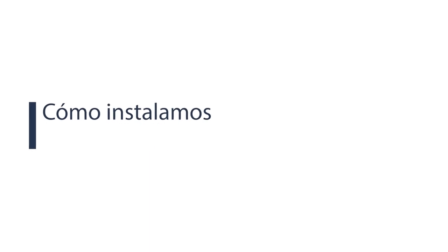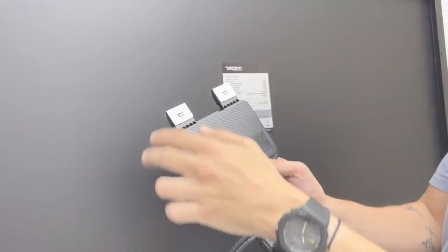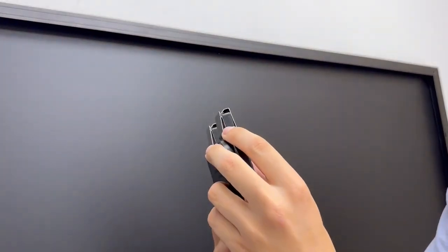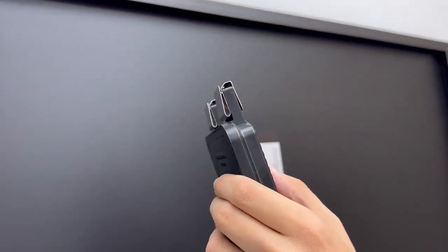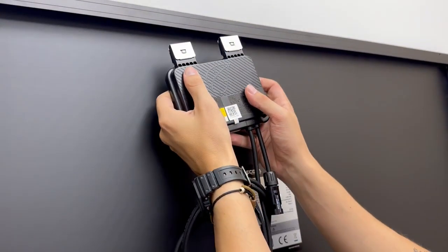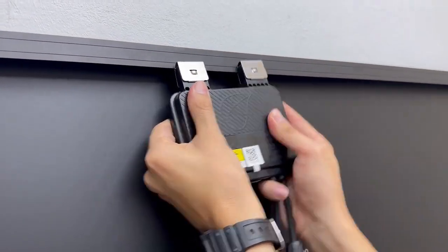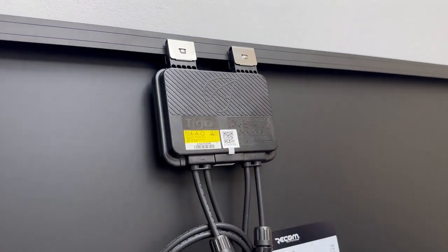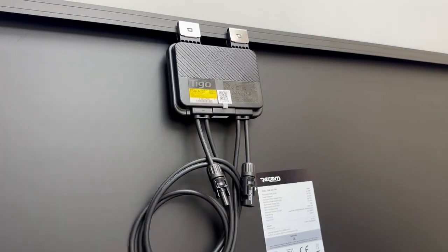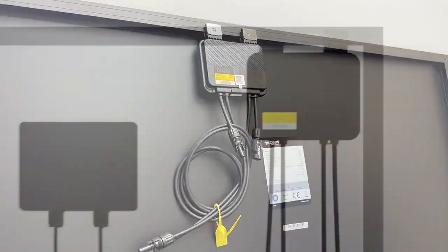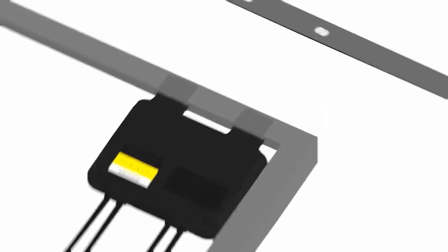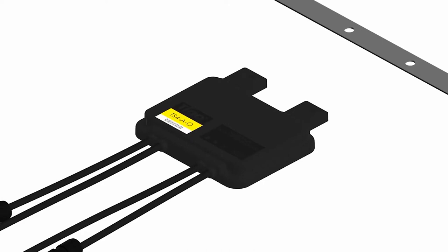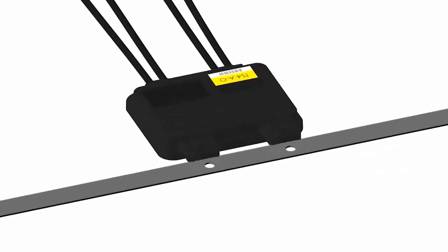But first of all, how do we install the optimizers on our PV panels? Attach the TS4 directly to the solar module frame. The TS4 can be mounted on top or on the sides of the module. In any case, do not install the optimizer with the wires facing upwards, as water could enter through the wires and damage them. If your PV module does not have a frame, remove the silver clips and screw them directly to the rails.